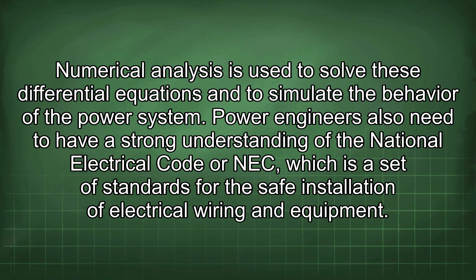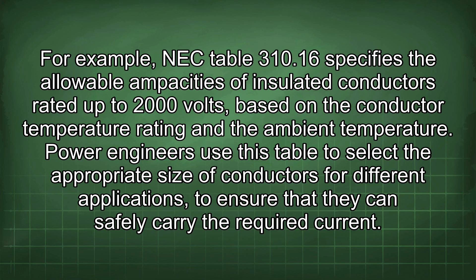The NEC covers a wide range of topics, including wiring methods, overcurrent protection, grounding, and equipment installation. Power engineers need to be familiar with the NEC in order to ensure that their designs comply with safety standards and to prevent electrical hazards. For example, NEC Table 310.16 specifies the allowable ampacities of insulated conductors rated up to 2000 volts based on the conductor temperature rating and the ambient temperature. Power engineers use this table to select the appropriate size of conductors for different applications to ensure that they can safely carry the required current.